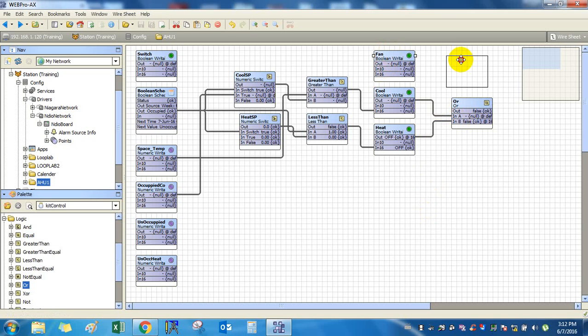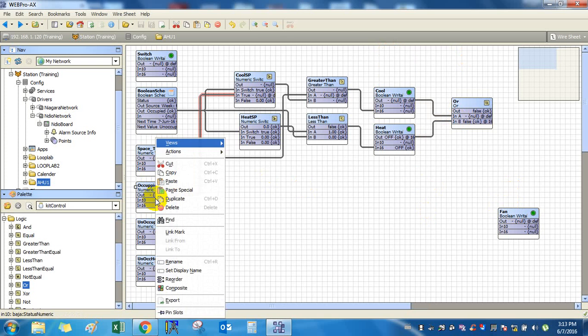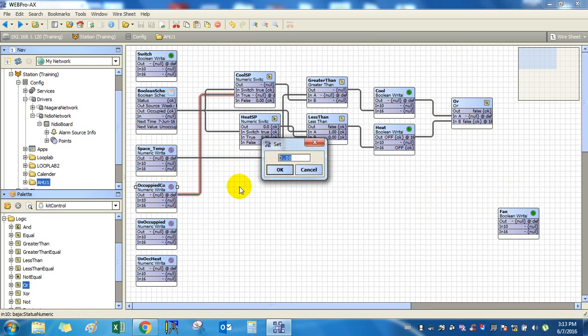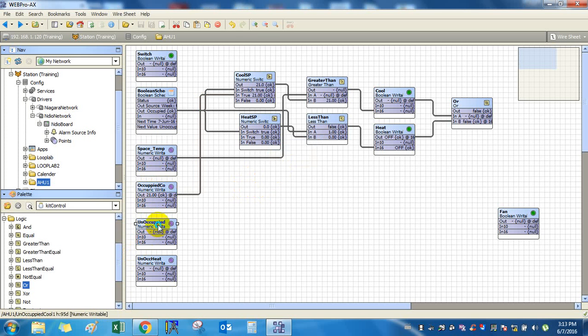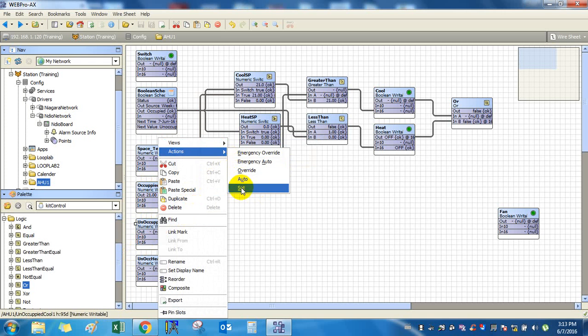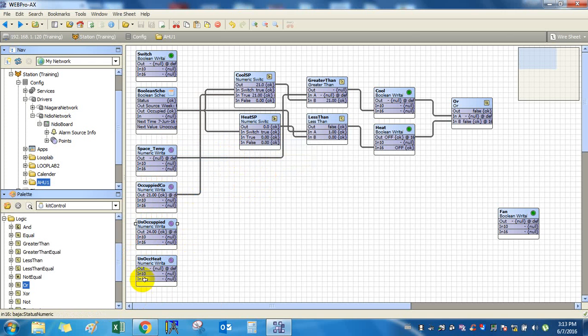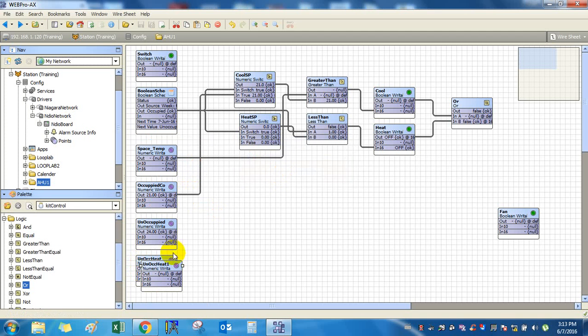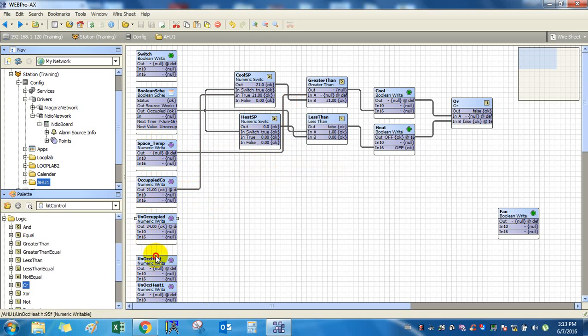Now set some values to the set points. Go to your occupancy point, right click, actions, set value. For occupied cool, let's say it's 21 degrees Celsius. Unoccupied cool, 24. Occupied heat as 19, and unoccupied heat as 17. Let's not use this switch for now, we will add it later.